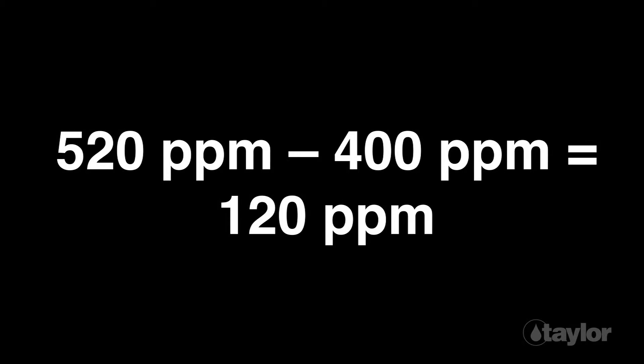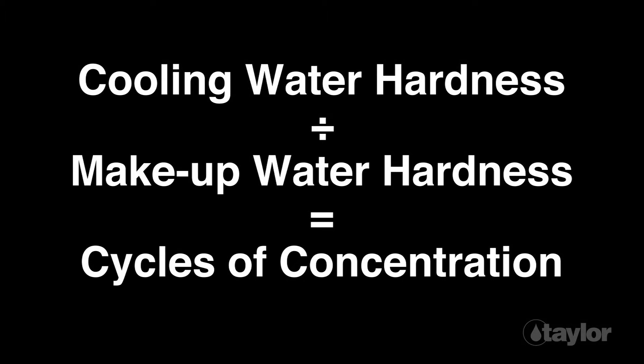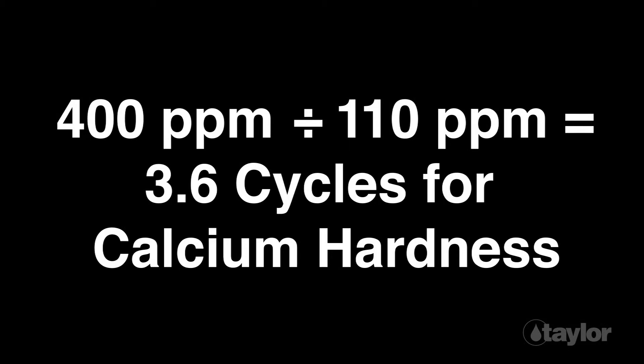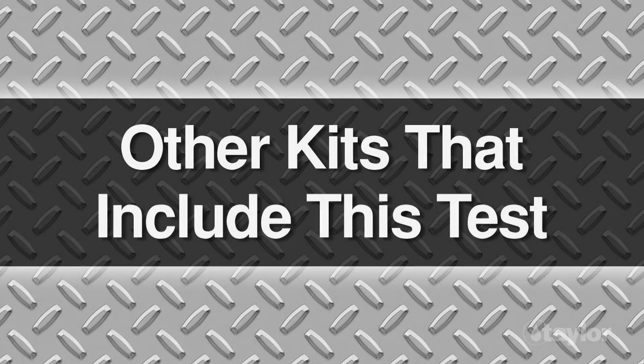Suppose the total hardness in the previous cooling water example was only 520 parts per million and the calcium hardness in the cooling water was 400 parts per million — then the magnesium hardness in the cooling water would be 120 parts per million. If we calculate the cycles of concentration for each hardness species, referred to as performing a hardness balance, we would find 3.7 cycles for total hardness, 3.6 cycles for calcium hardness, and 4 cycles for magnesium hardness. Since the calculated cycles of concentration are lower for total hardness and calcium hardness than for magnesium hardness, this could be an indication that scaling is occurring within the system.